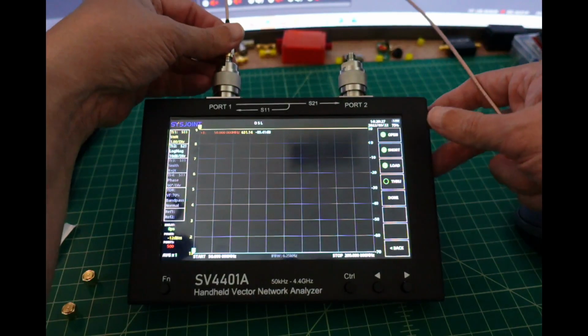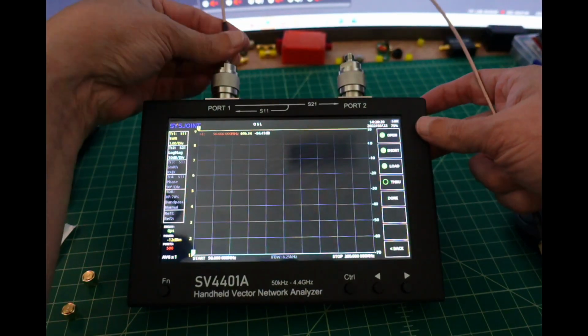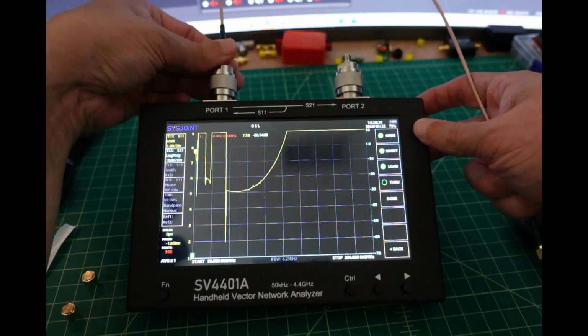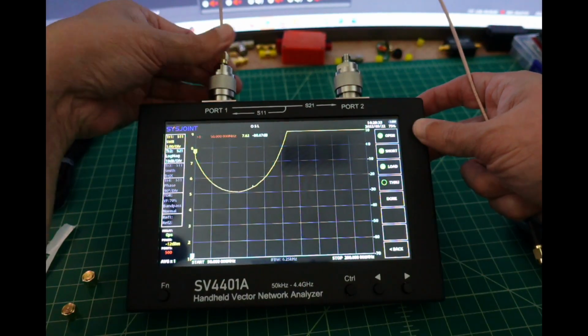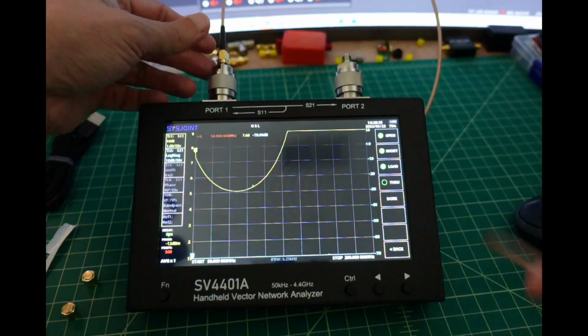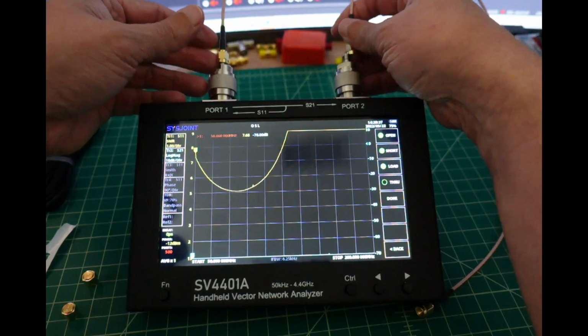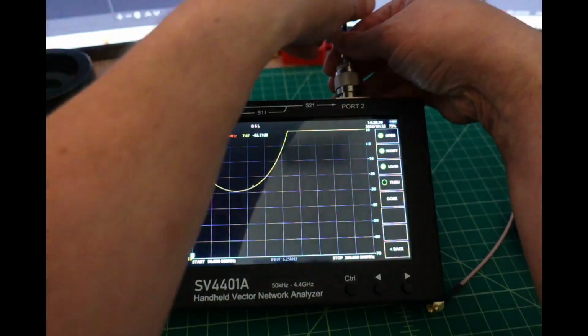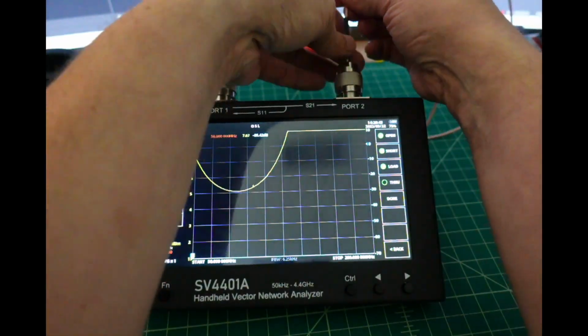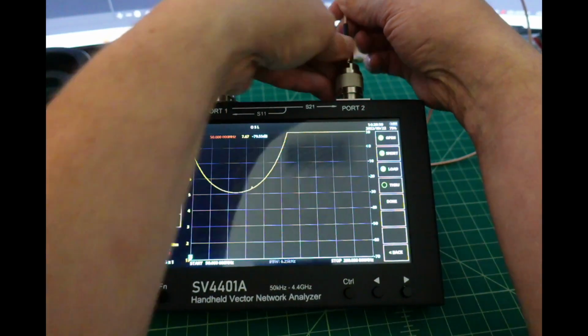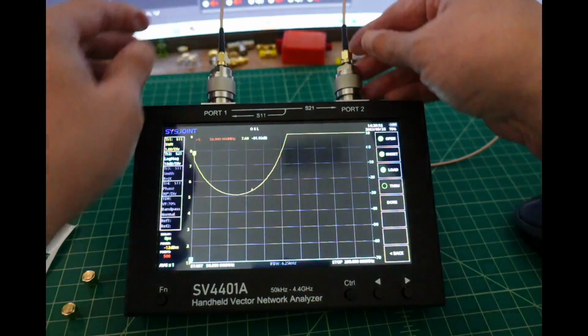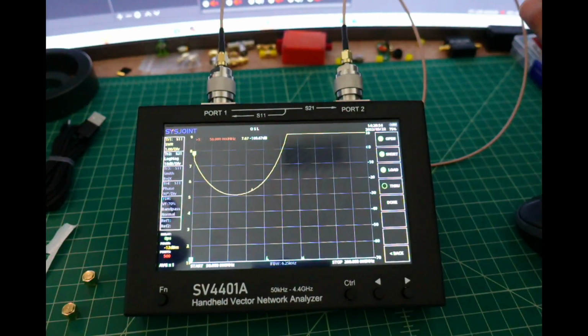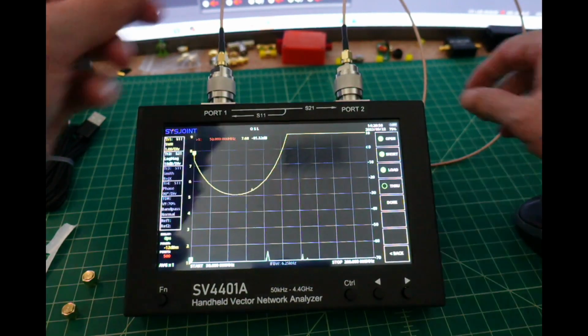And the way that we're going to do this, because of the test that we're going to do, we're going to test this against a filter. And the filter is going to require us to have two cables hooked up. So here's a second cable. And what this is doing is making sure that our calibration is taking these cables into consideration. So when we do our test, it's actually of the device. And then I'm going to use one of these through barrel connectors.